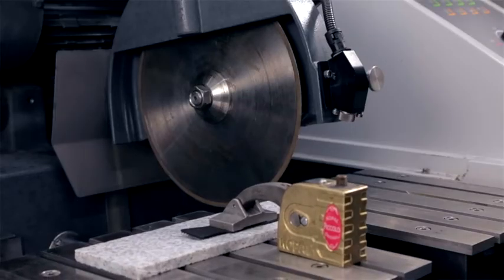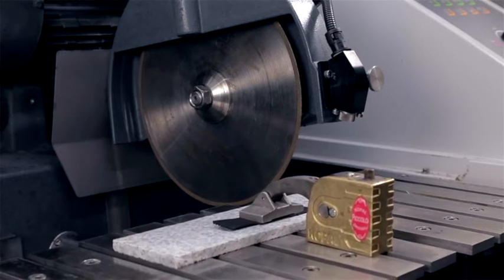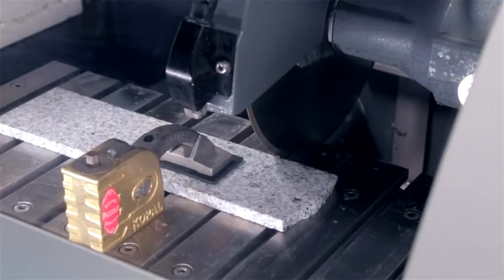The long-term cutoff wheels are steel-based with diamond abrasives on the perimeter. These are used to cut non-metallic specimens like ceramics, cemented carbides, or polymers. Since diamonds last a lot longer than silicon carbide and aluminum oxide abrasives, the long-term cutoff wheels last very long compared to the abrasive cutoff wheels. Due to the durability and the high cost of diamonds, the layer of abrasives around the perimeter is relatively thin.